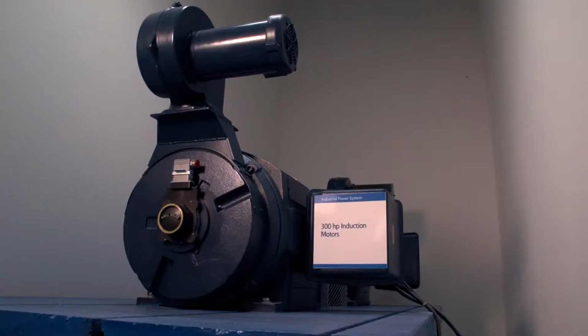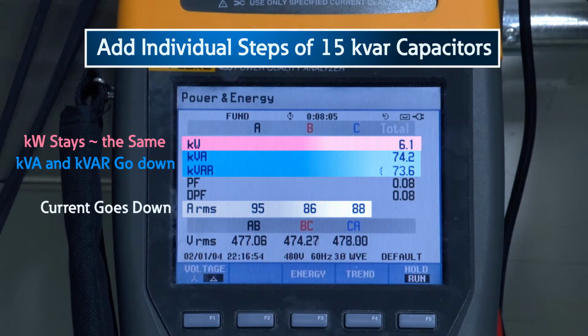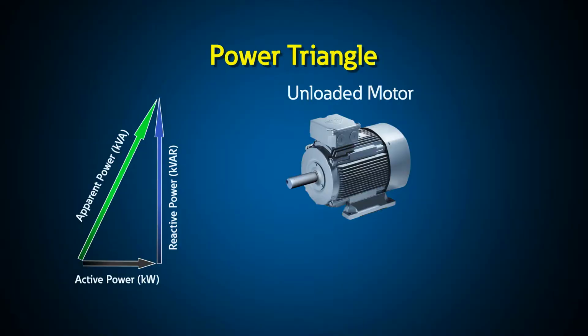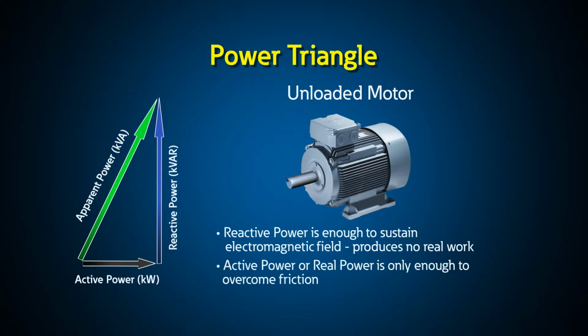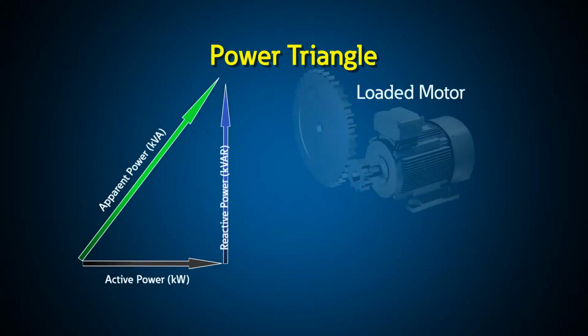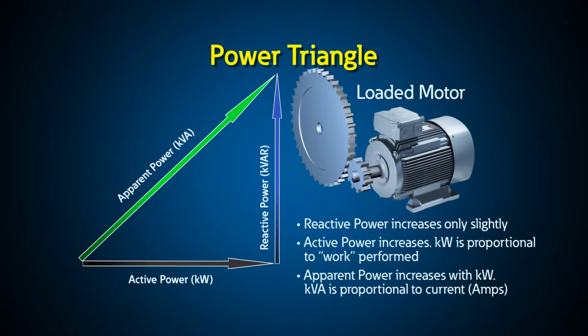What about large motors in commercial and industrial applications? Let's look at another demo, now using a 300 horsepower unloaded motor. Here, as we add individual steps of 15 kVAR capacitors, you can see the reduction in the current, or amps, as well as the kVAR and the kVA, with minimal change in kW. Unloaded motors show the most drastic effect for this demo, as they use very little real power, or kW, just enough to overcome friction, but they require reactive power, or kVAR, to create a magnetic field that allows the motor to spin. If we were to add a mechanical load to the motor, kWs would be required to drive the load.